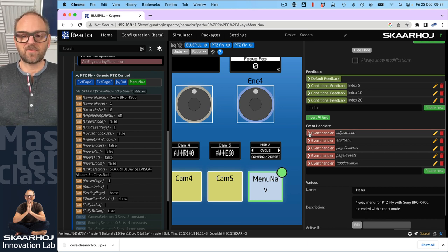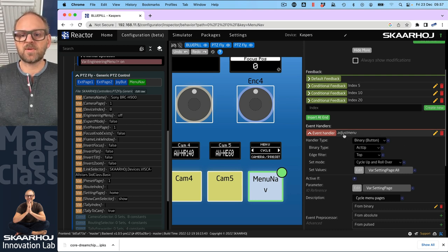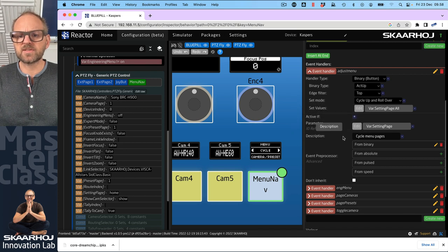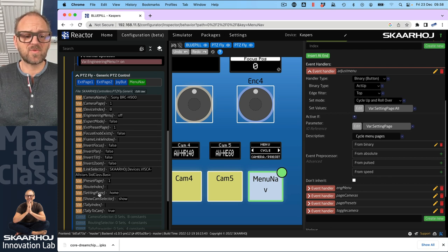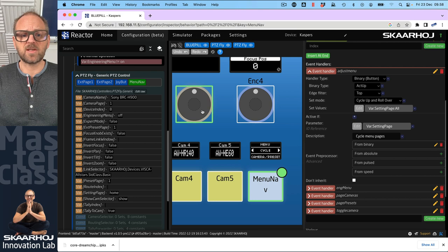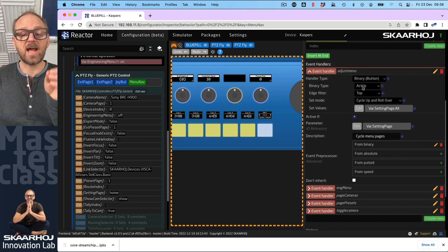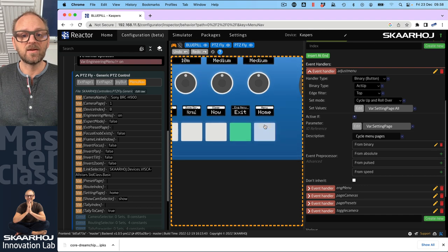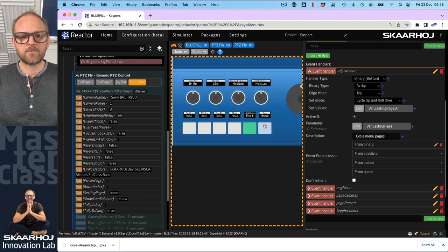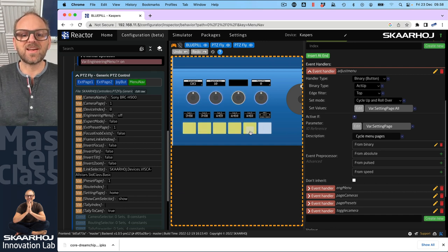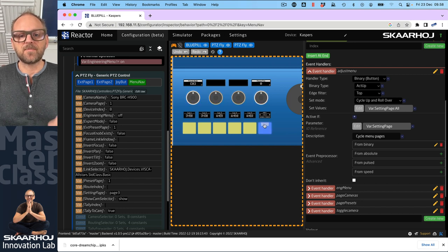Going into normal operation, finding the menu navigation button — this is the one. Using 'Show More' we can see a number of event handlers and default feedback going on, probably exposing features you didn't even know existed. Looking at the event handlers first — we have something called 'adjust menu'. The I/O reference is 'setting page' — we've seen setting page changes the menu on the upper buttons. Reacting on act up, with the top edge: if I press and hold then release, it cycles the menu.